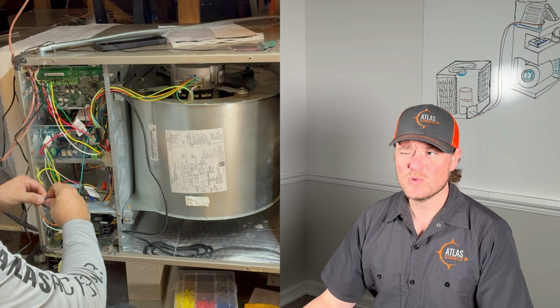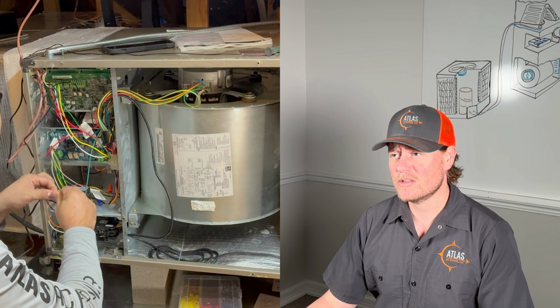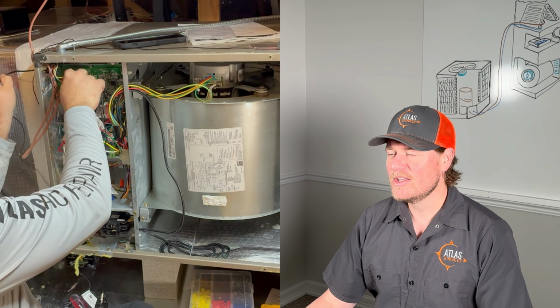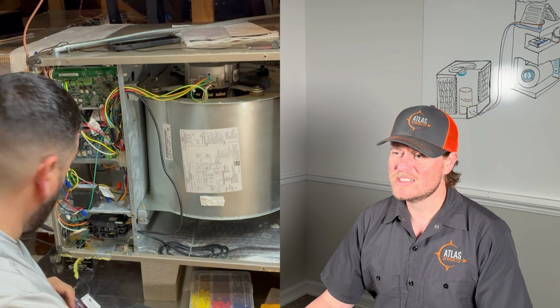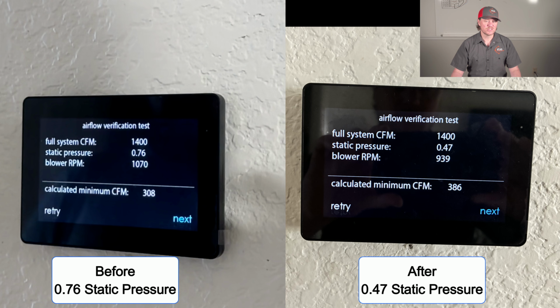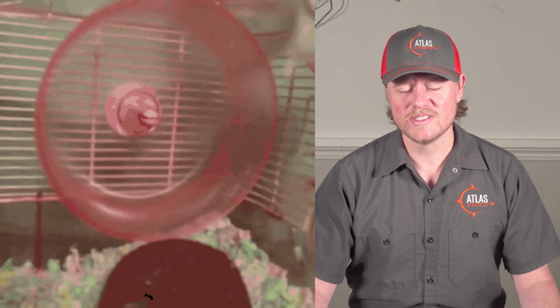And another thing that we really didn't cover in the video was the topic on the equipment itself. By increasing the overall size of the ductwork to where it needs to be for the equipment, it reduced the external static pressure to where it needs to be. Now the system's not going to be overworking when it's heating and cooling, resulting in fewer repairs and a longer life.